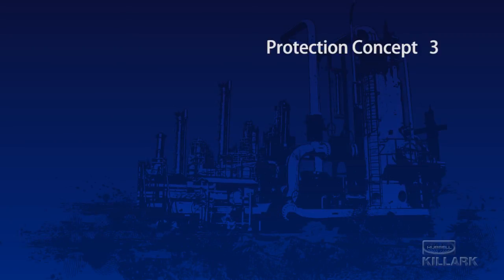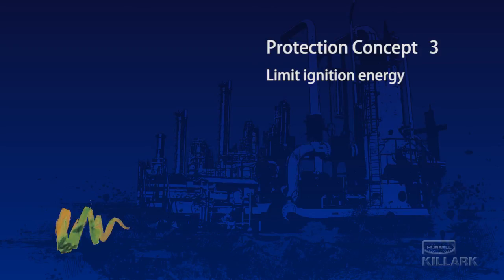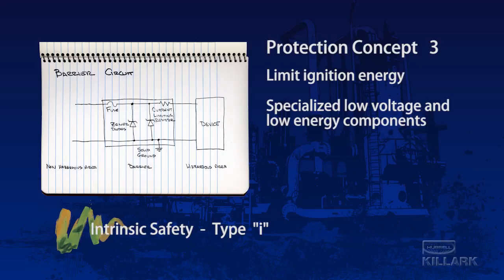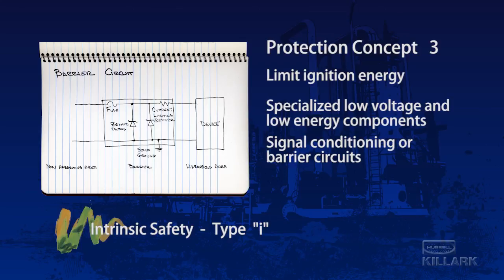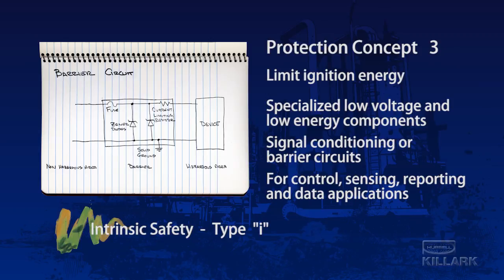The next protection concept depends on limiting the amount of energy available in a component to below the level that is necessary to initiate an explosive reaction in a flammable atmosphere. Known as intrinsic safety, Type I, this technique uses specialized low-voltage components within the hazardous location and additional signal conditioning components outside of the hazardous boundary or in flame-proof enclosures. This approach effectively removes the ignition leg of the fire triangle. Because of the exceptionally low energy levels allowed, intrinsic safety is generally restricted to control, sensing, reporting, and data applications.